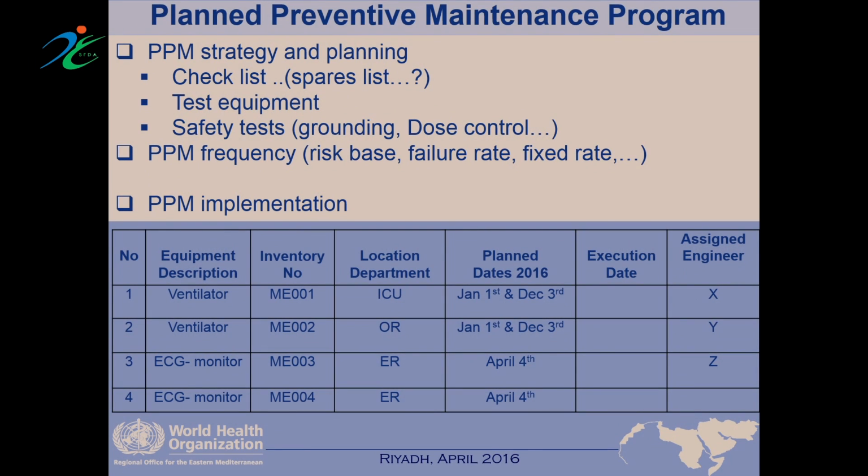And then once this is done, you put the date that this equipment was inspected, so that those kind of equipment which are classified as high risk equipment are definitely within the preventive plan, that you ensure those are running functionally, and while in the ICU or other departments they are using the equipment, you ensure the safety and the quality of those equipment.